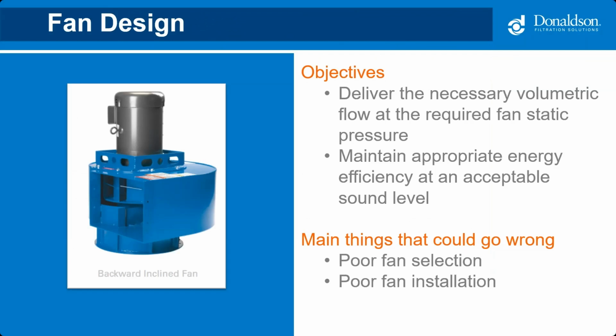The fan is like the heart of a local exhaust ventilation system. It has two responsibilities. First, a fan must deliver the necessary volumetric flow at the required static pressure to drive operations of the system. And since many dust collectors can operate with clean or dirty filters, the required airflow often has to be maintained over a range of static pressures. And secondly, the fan you select should be able to deliver the desired static and airflow with an appropriate energy efficiency at an acceptable sound level.